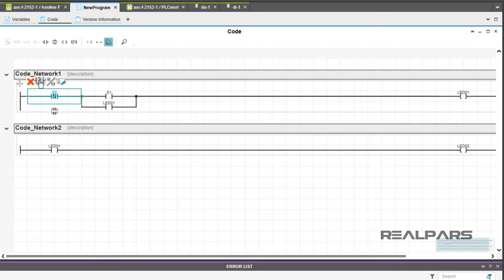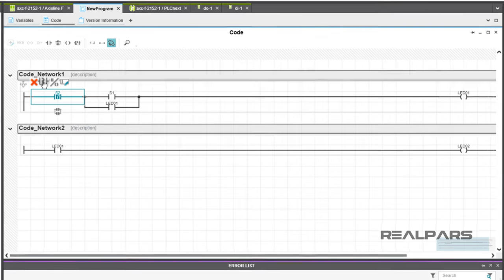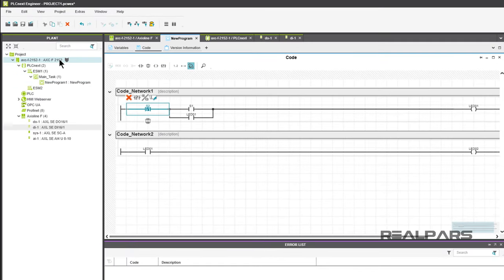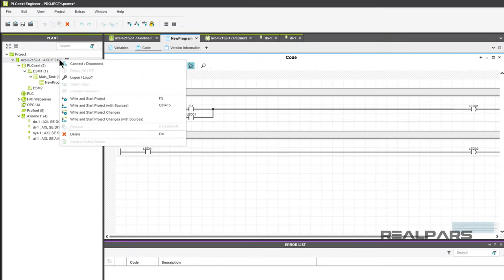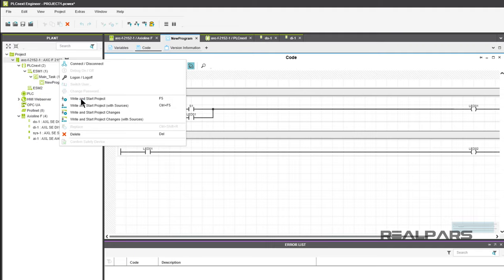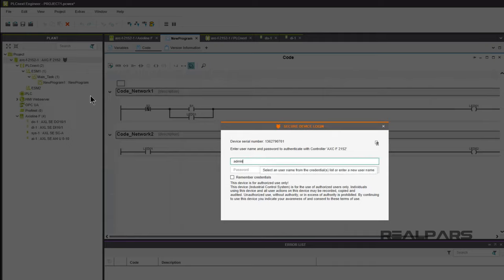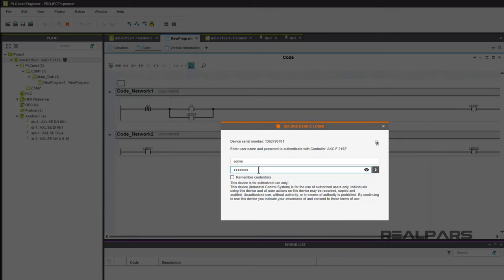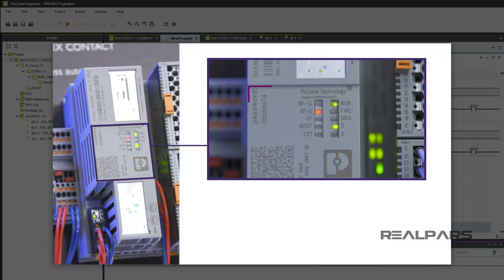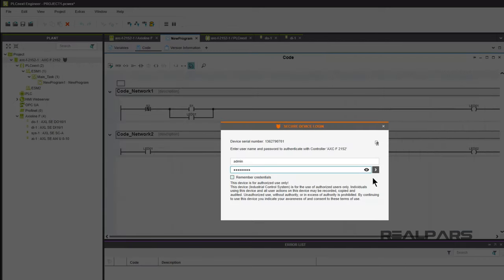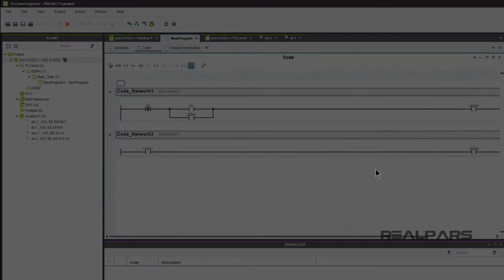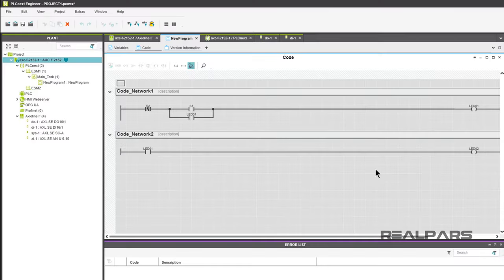Alright, we've constructed the ladder logic program. Now let's download it to the Starter Kit PLC and test it. Right-click on AXCF2152 under the Plant column. From the dropdown menu, choose Write and Start Project. There are a number of possible instances where you might see the Secure Device Login screen. If you do see this screen, enter Admin and the password for your controller. If you don't remember the password, it is stamped on the controller itself. The ladder logic program will download to the PLC and the program will start to run.